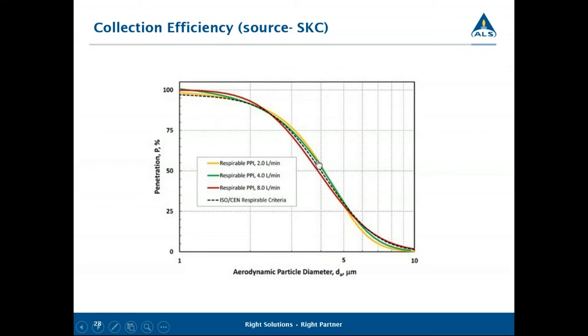Regardless of which unit you use, they all need to generate the same collection profile. When someone talks about a 50% cut point, they mean that if these units are properly deployed, about 50% of 4-micrometer diameter particulate will make it onto the filter, while collection efficiency increases sharply for smaller particles. It's important to use the recommended flow rates for each particular unit — adjusting flow rates shifts the collection curve and affects collection dynamics.